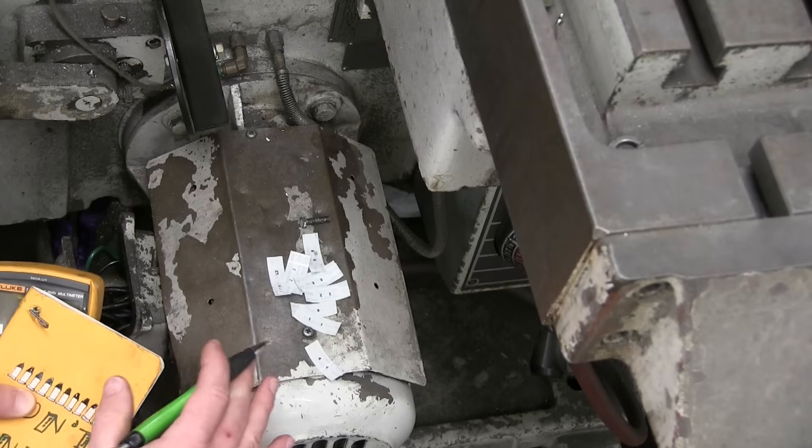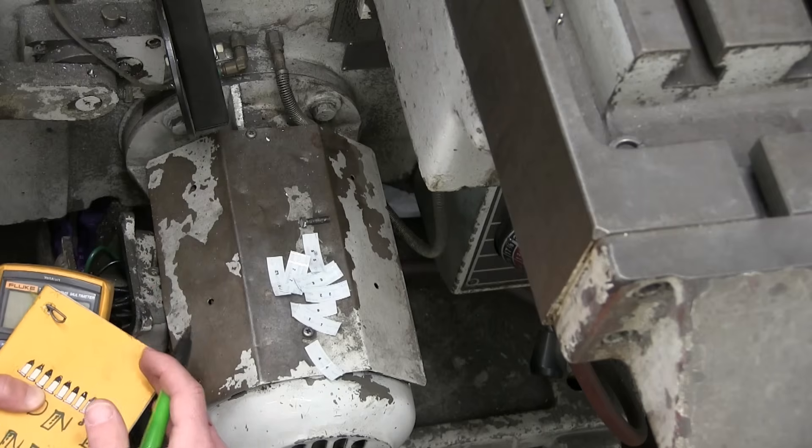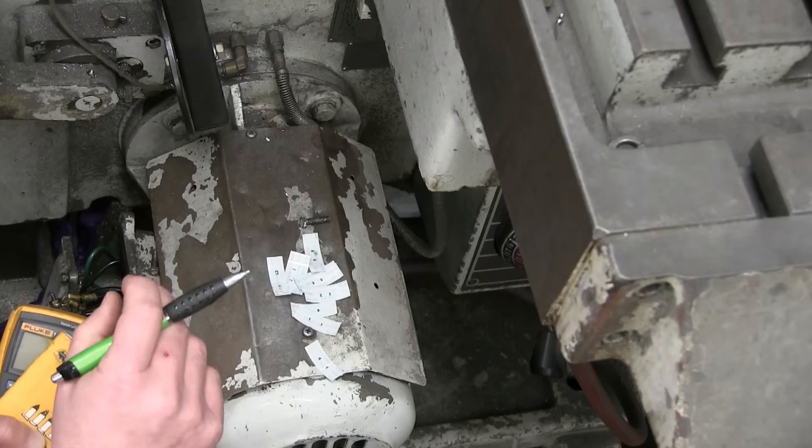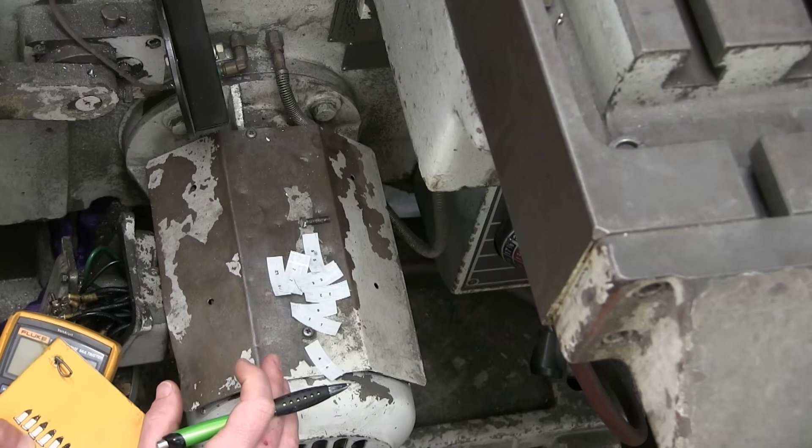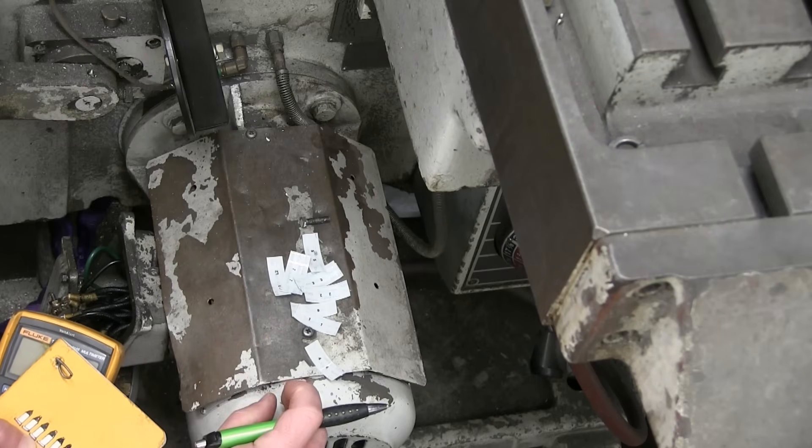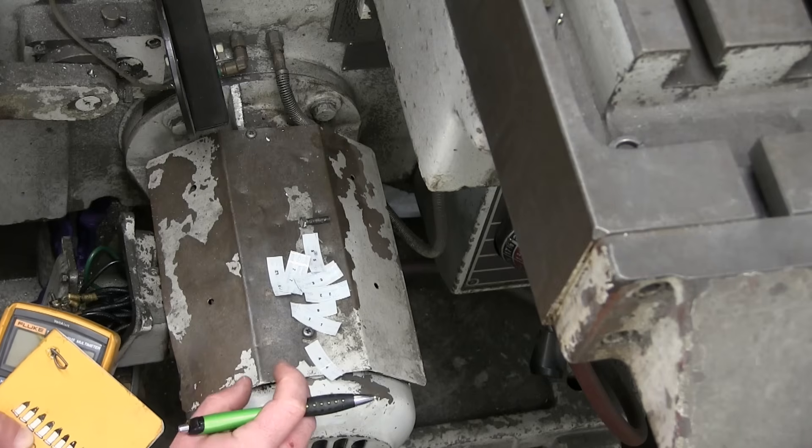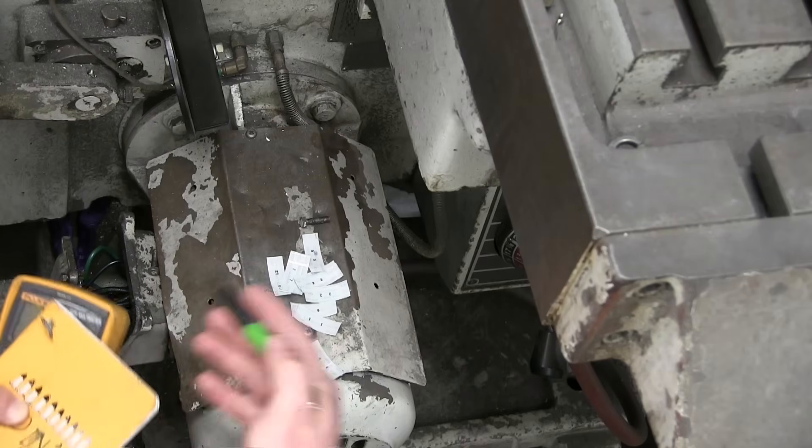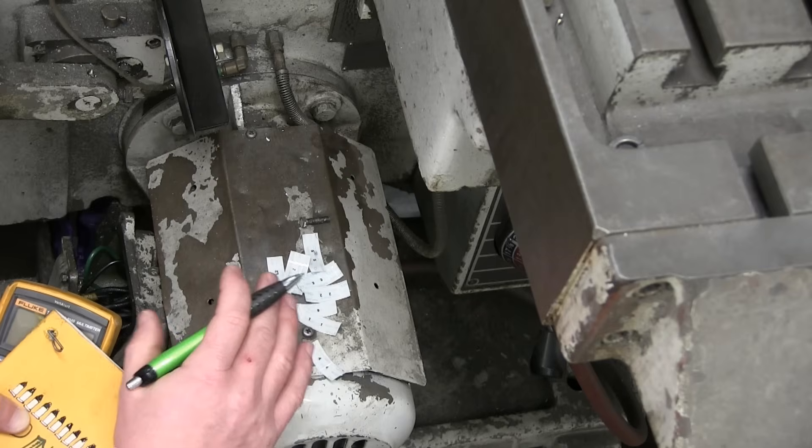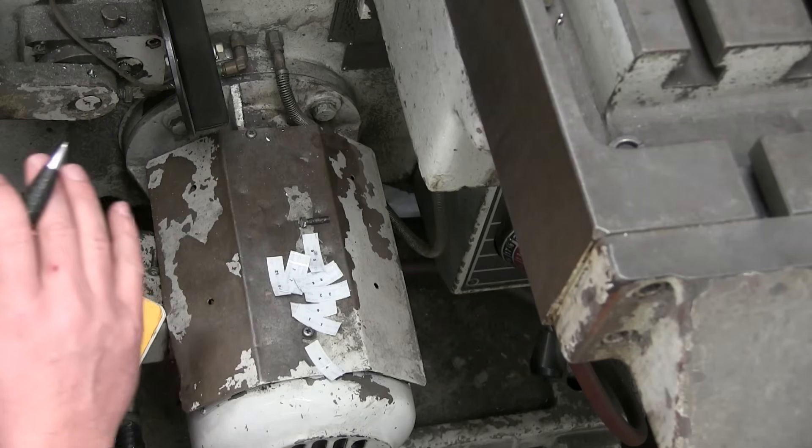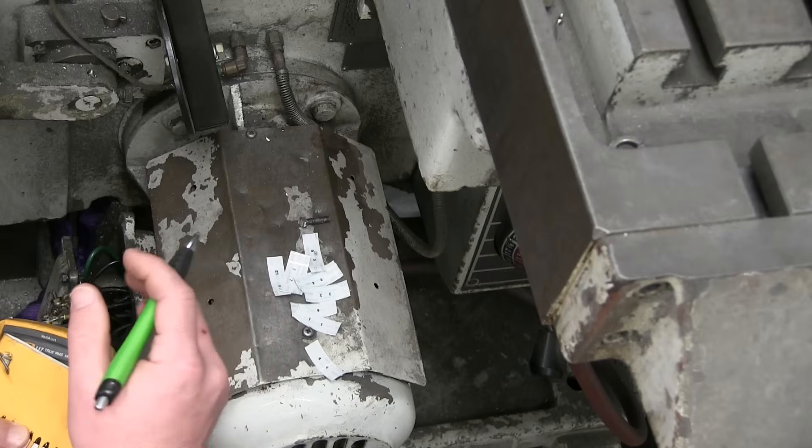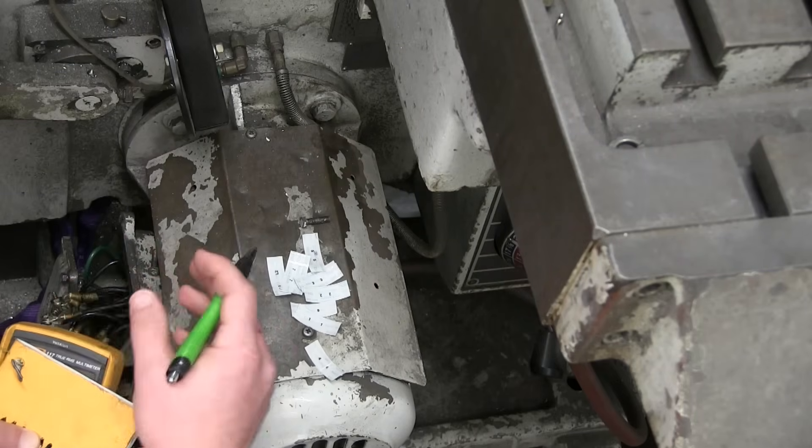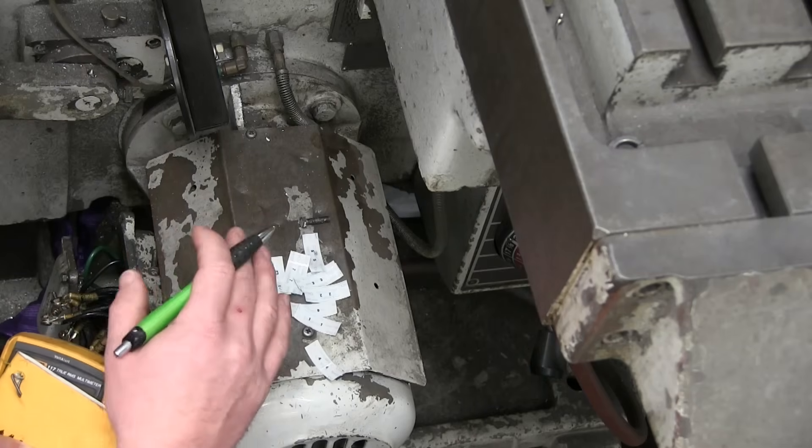Now this is running on 480 volts. We're gonna change that up to 220 because everything's wye, all the motors are wye motors, so we can parallel those wyes and run it on lower voltage. The case remains that we need to identify all these leads in order to get this thing to chooch on 220 volts. Now, first instinct when confuddled with the unknown is to grab the side cutters and start adding and subtracting jumpers and wires. But here's the thing, partner: you gotta give yourself time to think. Your brain is not a computer that goes through a list of instructions. You need time to break it down into little parts. If you don't understand the whole, you need to break it down into smaller bits that you do understand. Your brain needs time for lateral thinking to make connections, not make mistakes. So you've got to give yourself the time. If there's somebody breathing down your neck telling you go, go, go, hand them the side cutters and say give her, partner, because you need time. You got to have the confidence in your abilities to take the time to troubleshoot this properly.